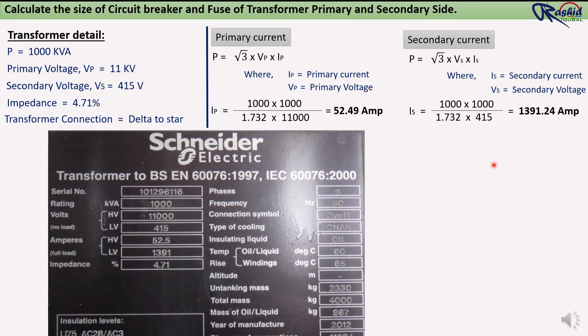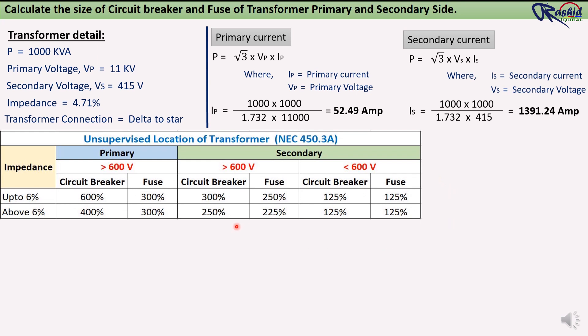After getting primary and secondary current, we can easily calculate circuit breaker or fuse size. For calculation, we will follow NEC 450.3 standard. If transformer impedance is up to 6%, we multiply a 600% safety factor by the primary current to get the proper circuit breaker size, and a 300% safety factor for fuse calculation. This applies only if primary voltage is more than 600 volts. In our example, primary voltage is 11,000 volts, so we will calculate as per this condition.